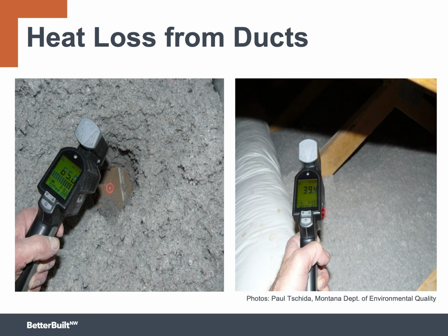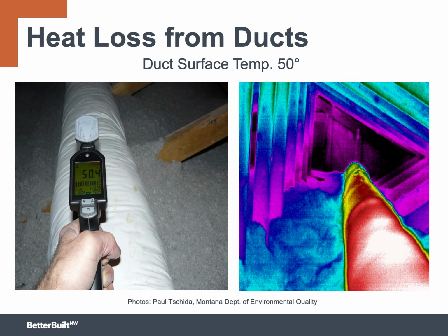These pictures really drive home the idea that the attic is outside the thermal boundary. On the left, you see an infrared thermometer. It shows the temperature of the ceiling drywall at about 65 degrees. So that's essentially the building's interior temperature. The attic air shown on the right is only about 39 degrees Fahrenheit, which is very close to the outdoor temperature on this particular day. This demonstrates very clearly that the attic is actually outside the thermal boundary. Now, if you look at the surface temperature of the duct itself, it's about 50 degrees.